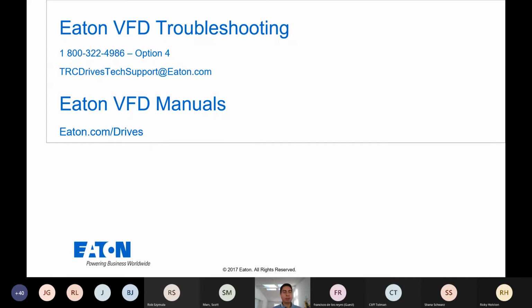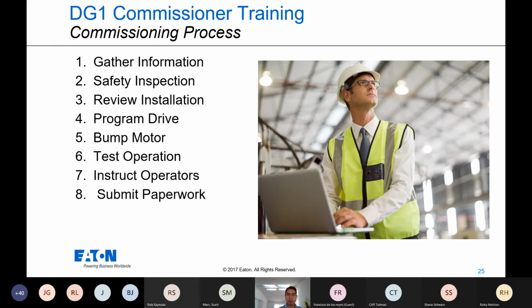So troubleshooting, before you go out and try and troubleshoot a VFD or find what problem you may have on your system, it is important that you know your VFD manufacturer's phone number, email, and that you have your manuals in hand. A lot of the time, the manuals can give you the basics so that you can yourself be able to troubleshoot the VFD or motor and machine. So the basics here is gather information.